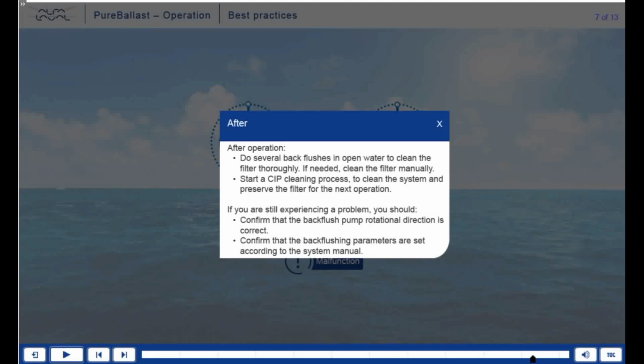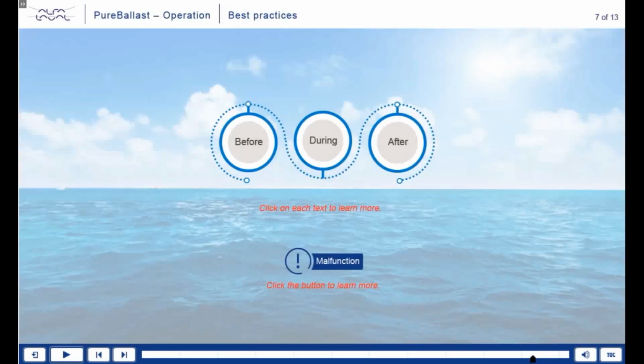If you are still experiencing a problem, you should confirm that the backflush pump rotational direction is correct. Confirm that the backflushing parameters are set according to the system manual. The parameters should normally not be changed after commissioning, but can, if needed, be adjusted for specific circumstances. Alfa Laval shall be consulted before changing the parameters. Click the button to learn more.